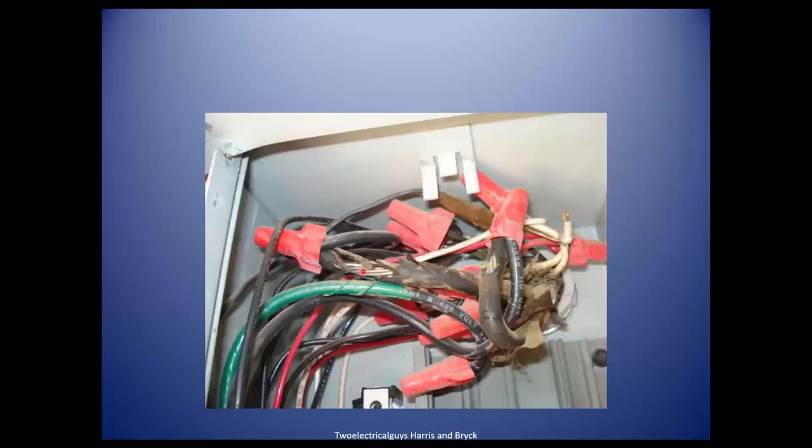Look at all this exposed wire. That's copper coated with tin — it's very old and the insulation fell off the wire. Not every wire was cloth-covered — there was single-braid and double-braid, then plastic type that would sometimes dry out and crack. This wire potentially could be aluminum versus tin-coated copper, but it doesn't matter — it's still wrong.